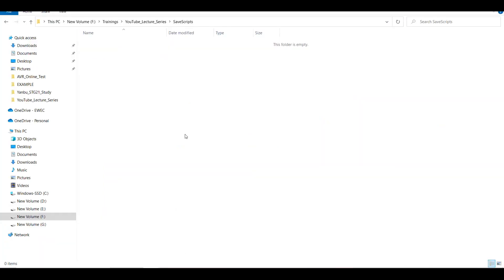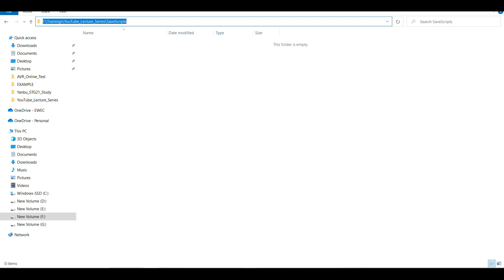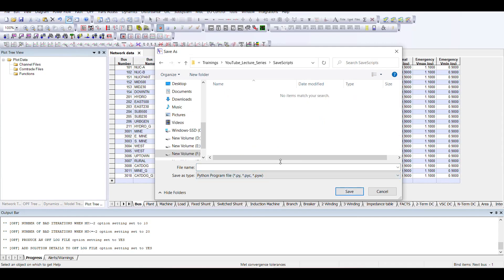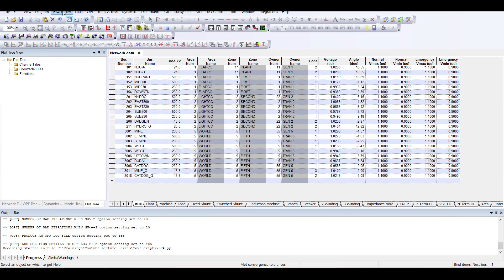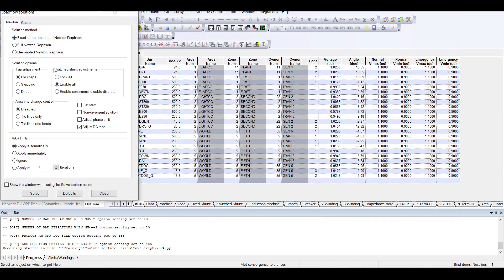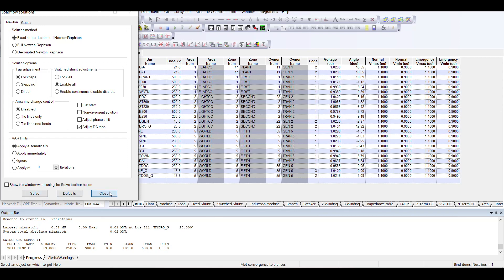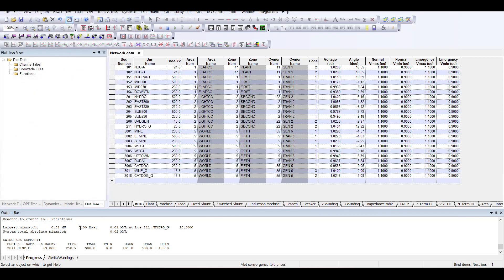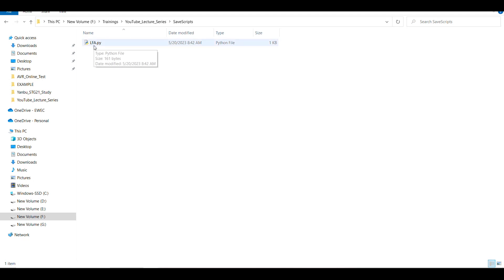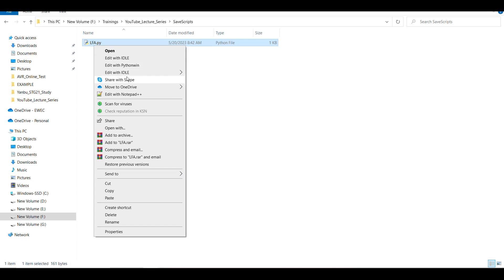I am going to record the load flow analysis task and save it at a particular location. I'll copy the path, navigate to it, and define the file as 'load_flow_analysis' so the Python script gets saved there. Then I'll go to Power Flow > Solutions > Solve, selecting the fixed slope decoupled Newton-Raphson method with all default settings. Once I press Solve, the case is solved in one iteration and the activity is recorded. I'll press Stop to end the recording.